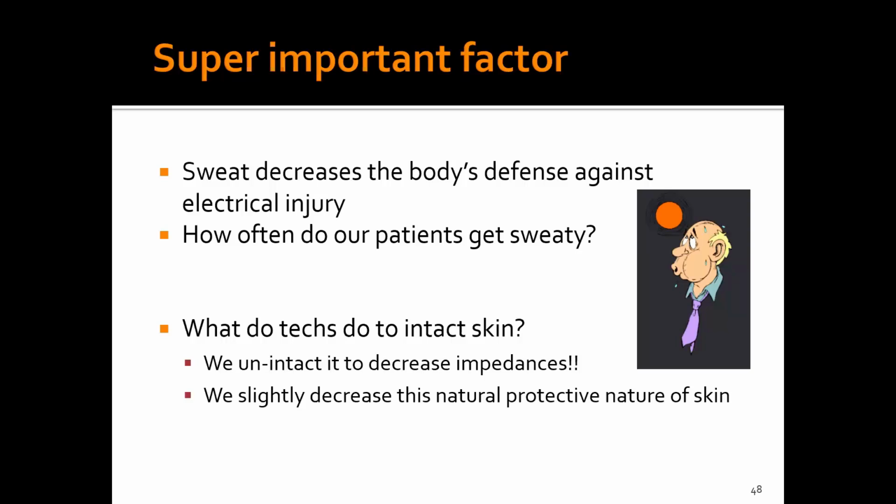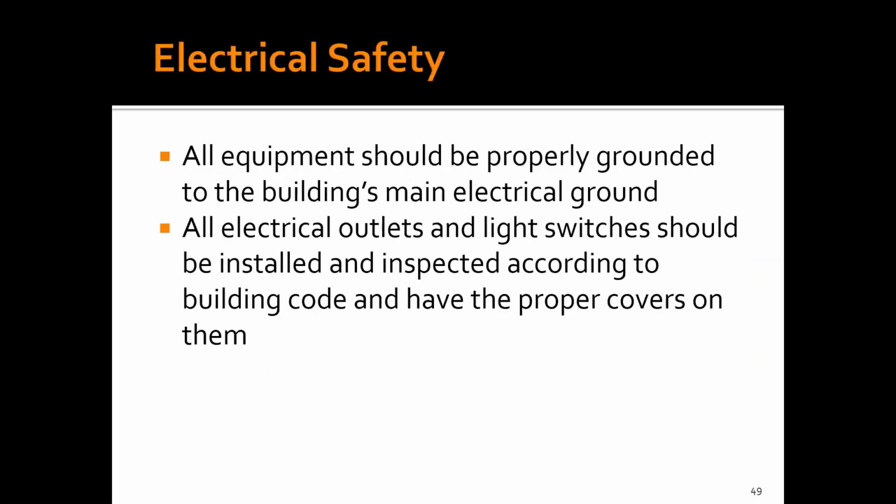We're using an electrolyte paste that has sand in it, and we are unintacting their skin to abrade it, not entirely breaking their skin. It's not open, but microscopically, yes, we're abrading their skin to reduce the resistance. And think back to that electrical theory: resistance is one thing that can help protect a person from shock, and we're reducing that even more. We're removing the natural protective nature of the skin, so if there were to be a current or something to happen, we're making our patients more electrically susceptible to the negative impact of that.